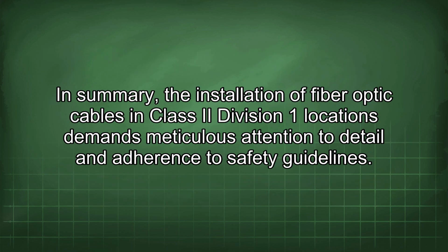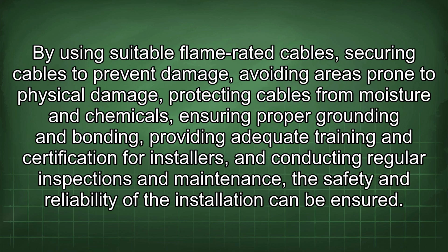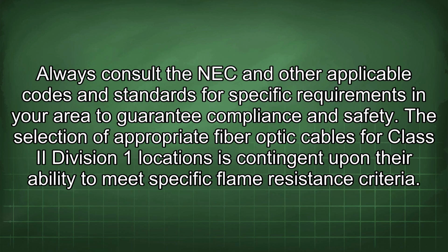In summary, the installation of fiber optic cables in Class II Division 1 locations demands meticulous attention to detail and adherence to safety guidelines. By using suitable flame-rated cables, securing cables to prevent damage, avoiding areas prone to physical damage, protecting cables from moisture and chemicals, ensuring proper grounding and bonding, providing adequate training and certification for installers, and conducting regular inspections and maintenance, the safety and reliability of the installation can be ensured. Always consult the NEC and other applicable codes and standards for specific requirements in your area to guarantee compliance and safety.